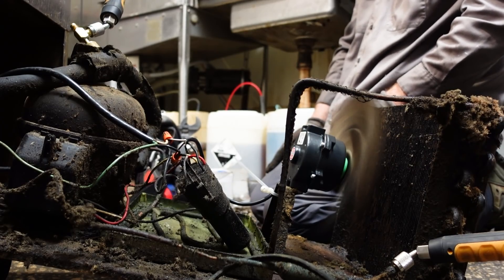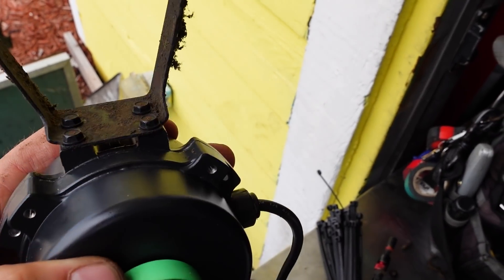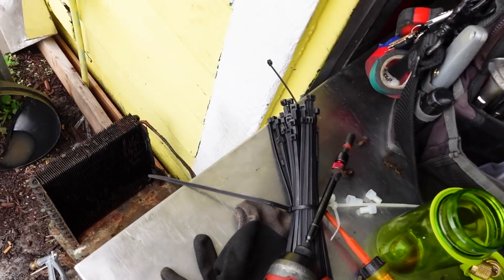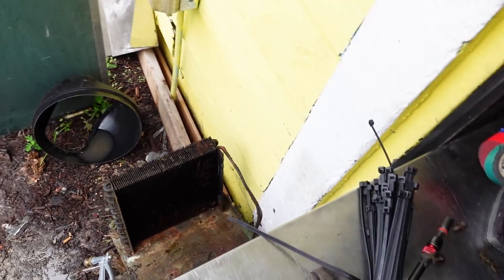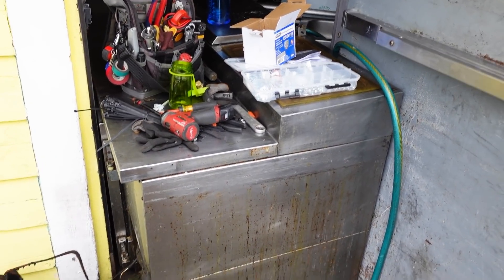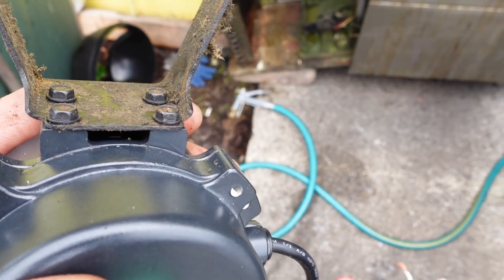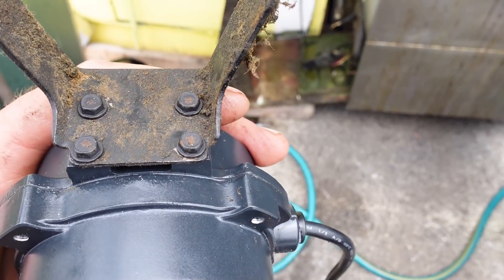Do you see a path to get this thing out of here? The magic of a Dremel and a cutoff wheel — I made these screws shorter for the fan motor. We cleaned out the coil. Cleaning off the blade. Since this thing now is a known running unit, going to scrape that blade clean with a brush and put this all back together. We got it barely outside the door enough to be able to clean it without making a mess in the kitchen. I just didn't have any washers, so five minutes and a Dremel. Those things will save you so much time if you've got one on your truck.